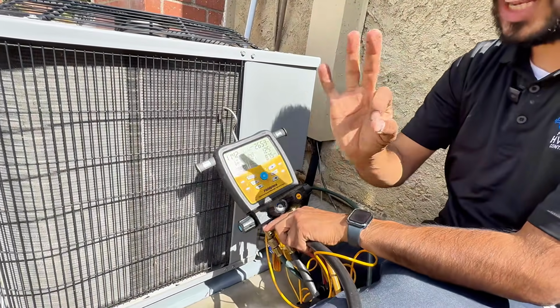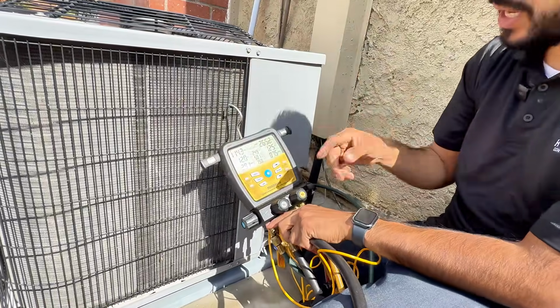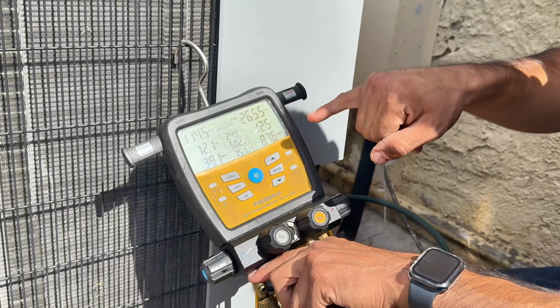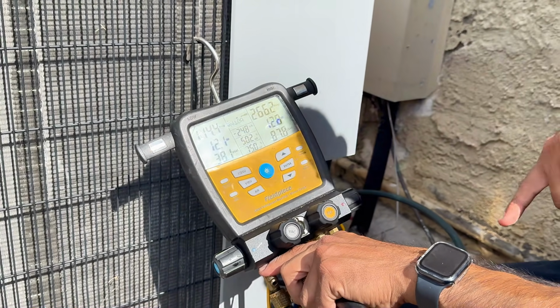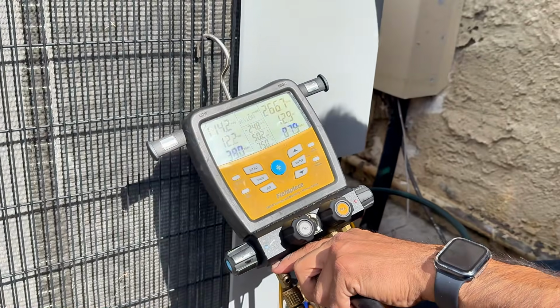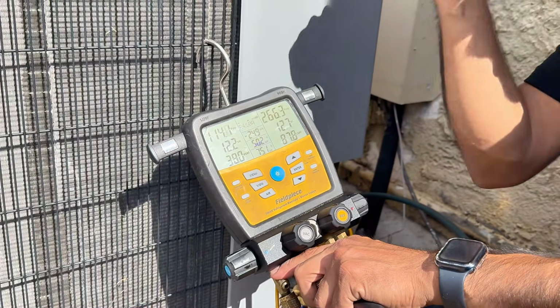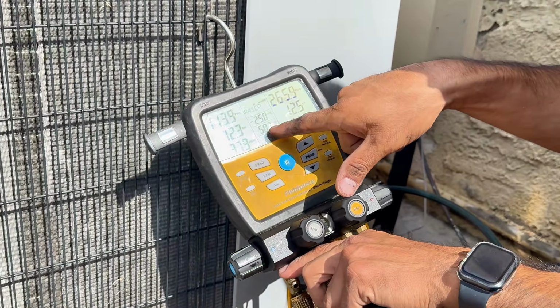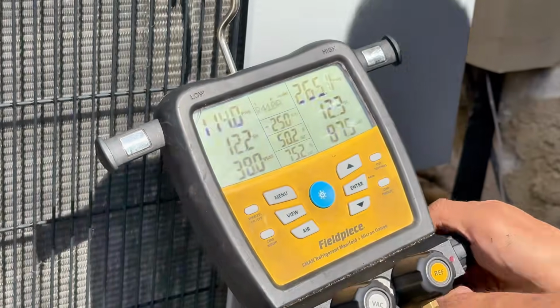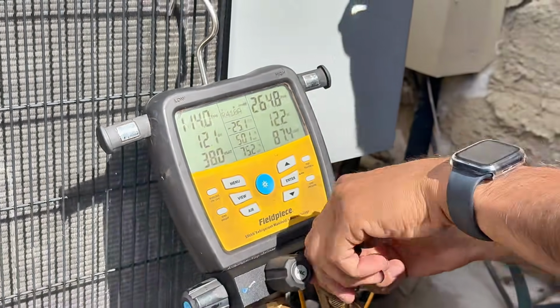Look at my subcool. That's telling me that I have enough liquid column behind the liquid, and I'm getting a subcool of 12 degrees, which is condensing temperature minus my liquid line temperature. I have a 12-degree subcooling. So looking at this, it looks like it's good on charge. And we're still going to check delta T inside. But my superheat is suction line temperature 50 minus my evaporator 38, which is 12 degrees. So this system is operating pretty good right now.